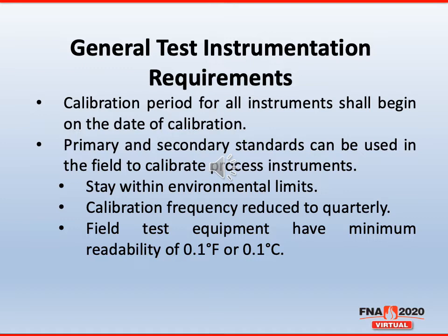Lastly, field test instruments. These would be your instruments that are used to do system accuracy testing or calibration of the instrumentation on the furnaces, or your temperature uniformity survey recorder data acquisition. They now have to have a minimum readability of 0.1 degree Fahrenheit or 0.1 degrees Celsius. Some of the test instruments out there that are being utilized now, once the readings get above 1,000 degrees, lose their decimal point. So that's one change that people should be aware of when it comes to your test instrumentation.